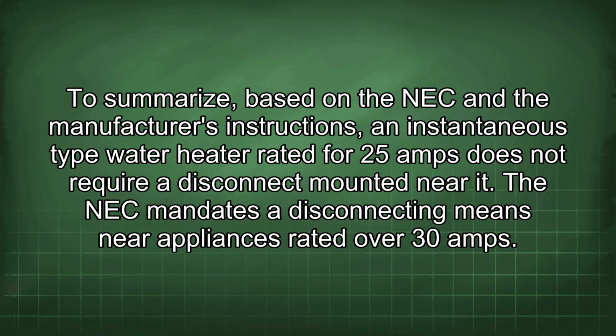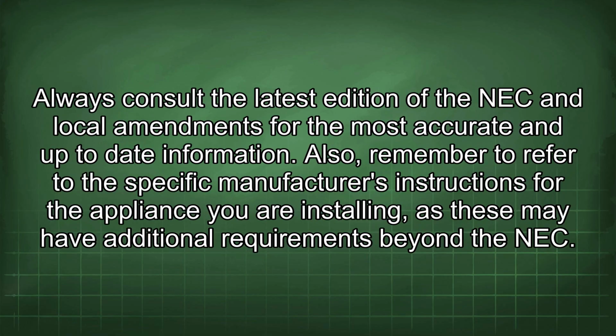To summarize, based on the NEC and the manufacturer's instructions, an instantaneous type water heater rated for 25 amps does not require a disconnect mounted near it. The NEC mandates a disconnecting means near appliances rated over 30 amps. Always consult the latest edition of the NEC and local amendments for the most accurate and up-to-date information. Also, remember to refer to the specific manufacturer's instructions for the appliance you are installing, as these may have additional requirements beyond the NEC.